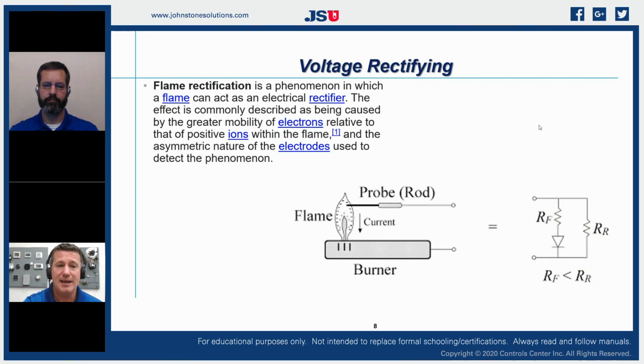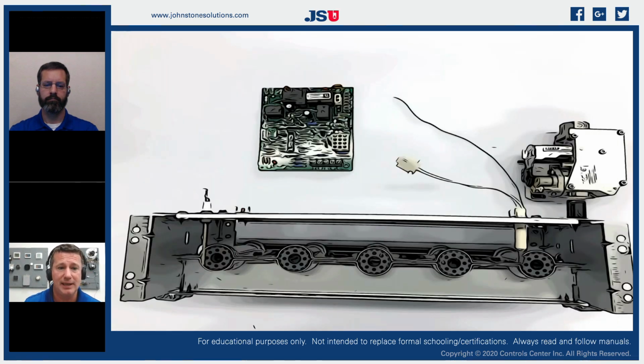So the interesting effect of flame rectification is as our electrons move across a flame, they don't have a constant path. Remember, in that combustion process, we have a lot of carbon molecules that are passing through our flame still, right? Even through complete combustion, we have carbon molecules. And we have moisture that is now being condensed out of the air. As our electrons try to pass through that flame, they are conductive across the flame because of our carbon molecules. Carbon is a conductor of electricity. So we actually allow our electrons to try to make their way back to ground through the flame. And in that process, we're actually creating a load on the flame as it's making its way to ground. That was never taught when we moved into flame rectification. What we are doing in flame rectification is exactly that.